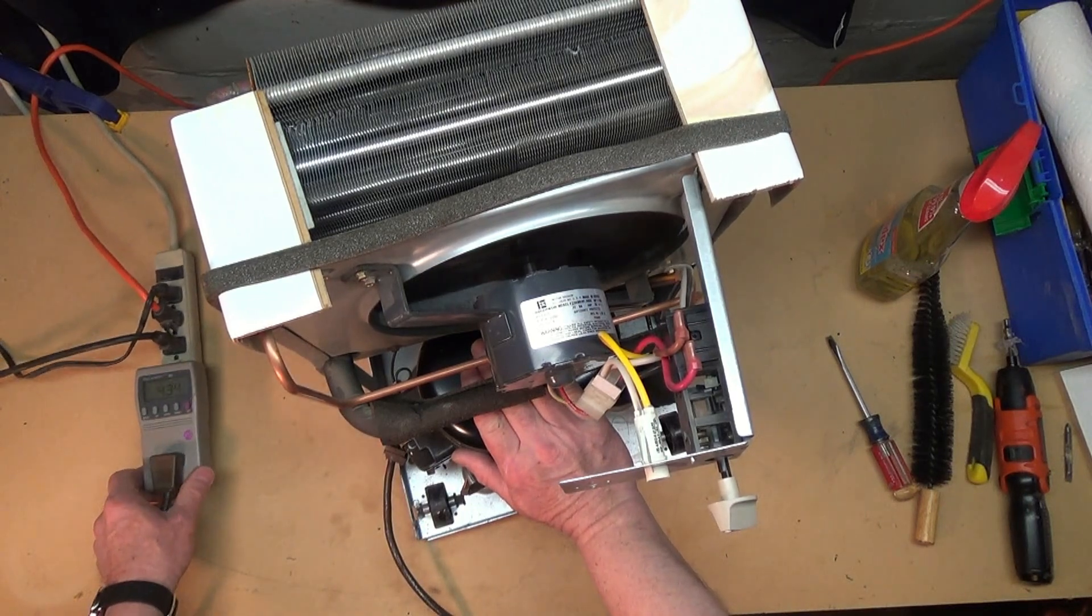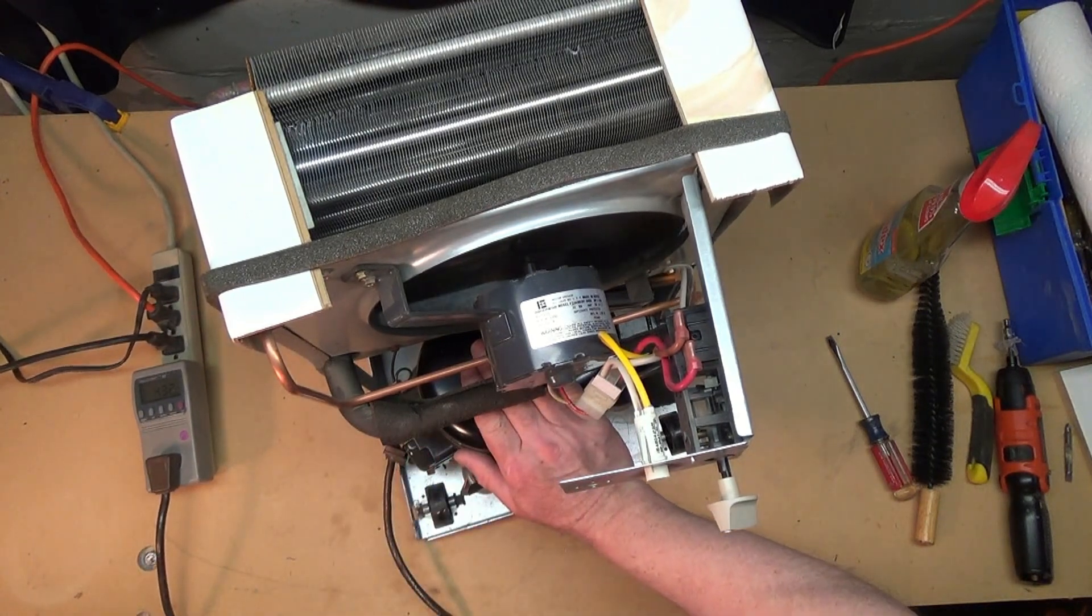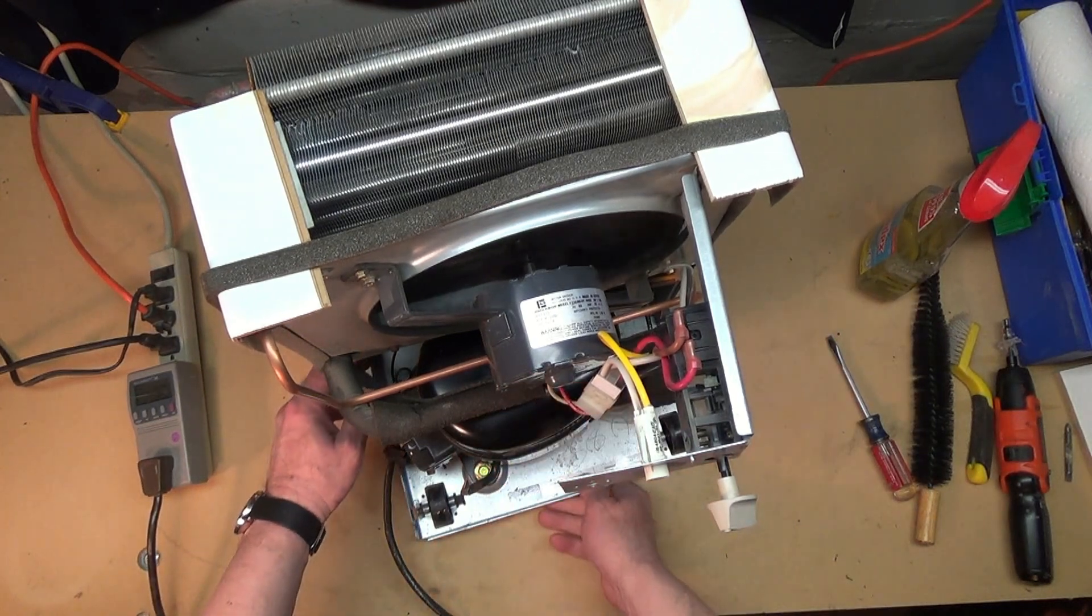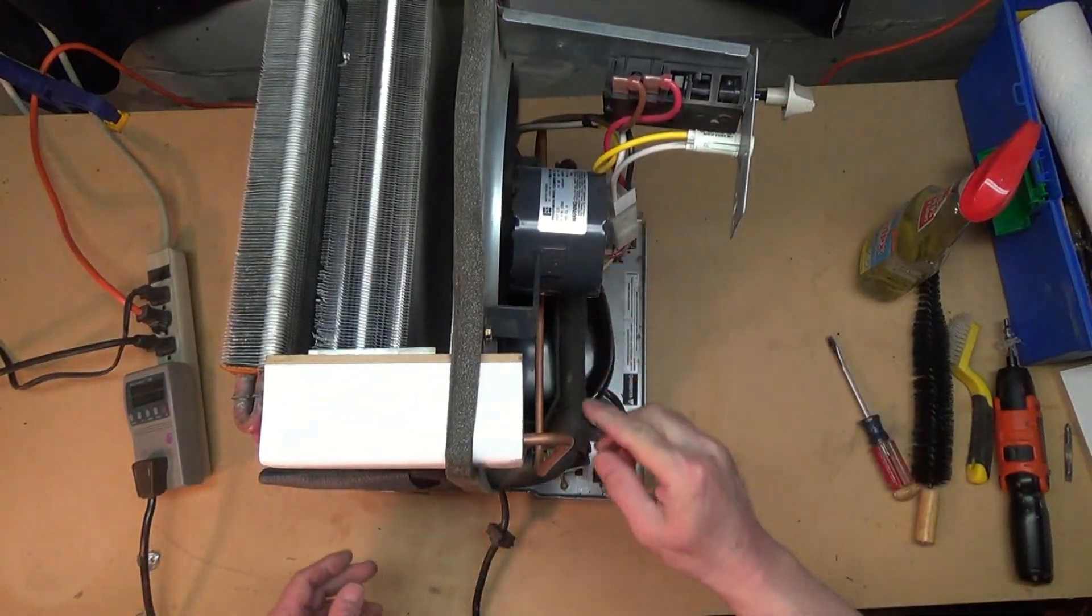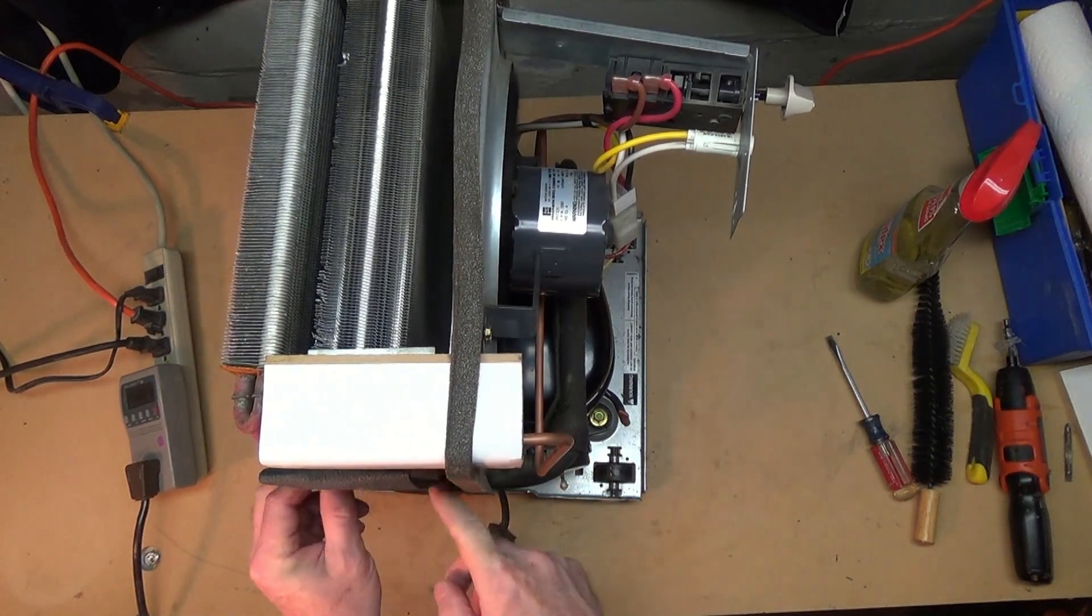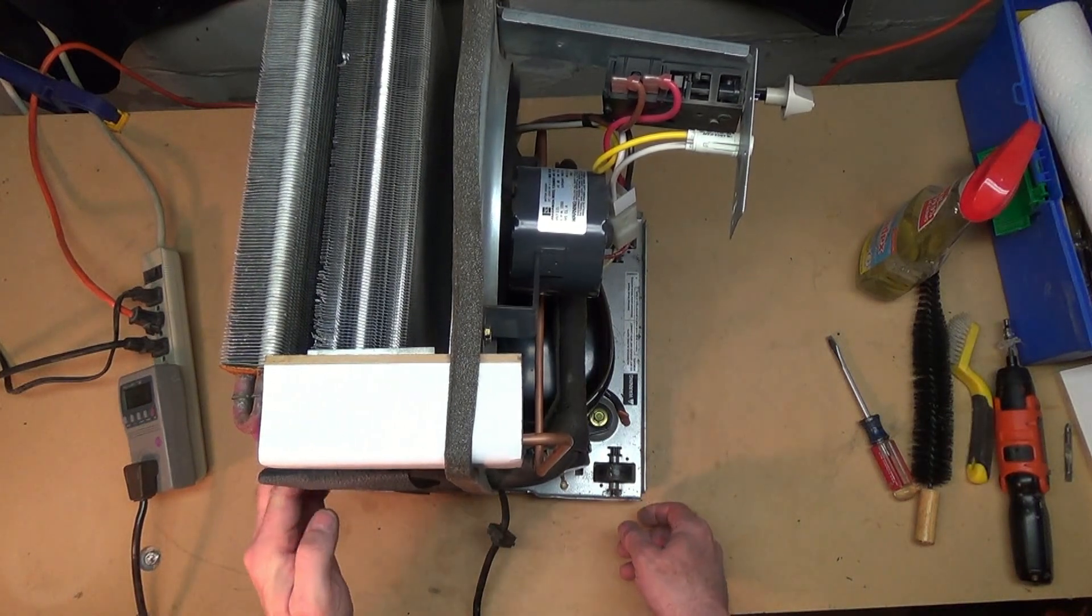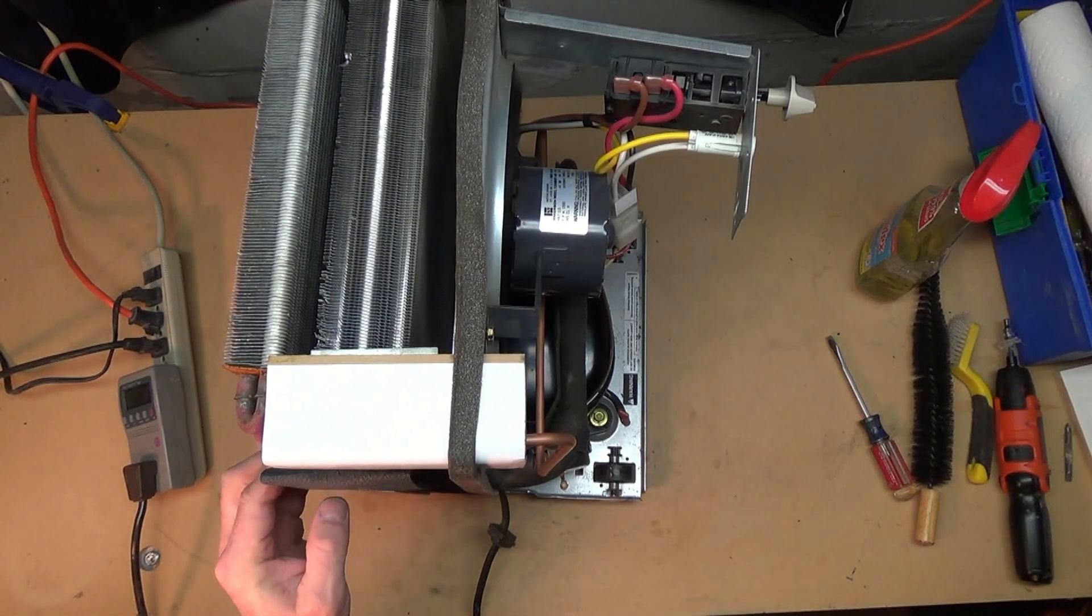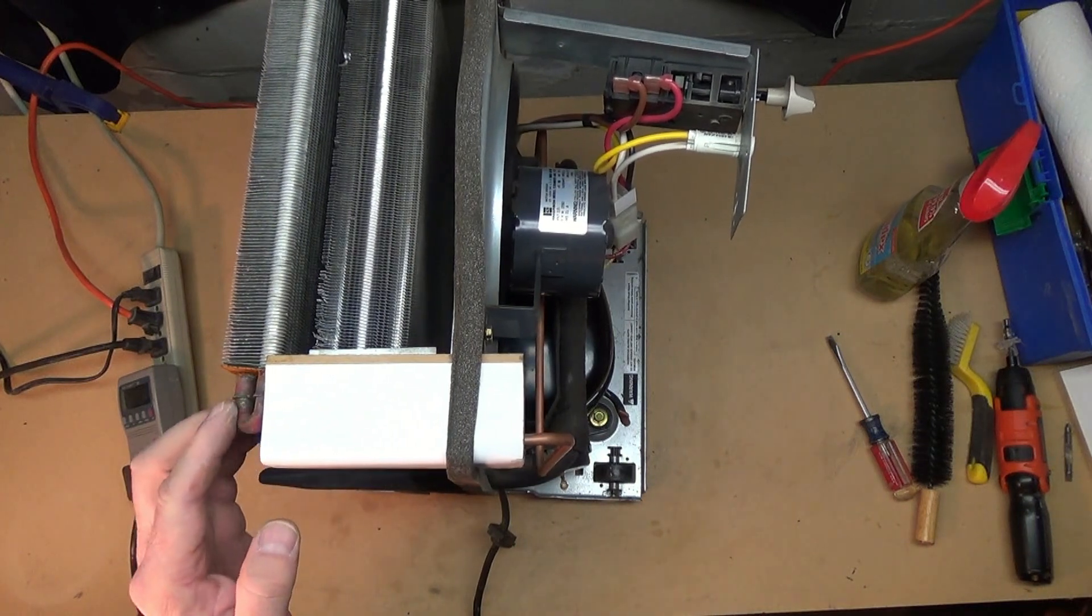And I can feel that the compressor is running. The fan itself would use about 40 watts when it was running all by itself. So with the compressor running a minute or two, what we should feel, if we follow this insulated back over to here, we should start to feel cool, which I am. Already feeling coolness in the coils, and that's what we're supposed to feel.